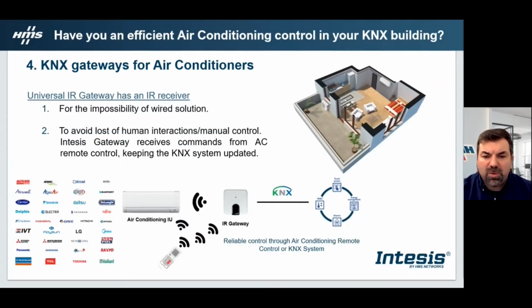Finally, we have our universal infrared gateway to answer to the impossibility of wired solutions. Beyond that, the infrared gateway is developed to minimize the loss of manual controls. As we can see in the image, when we change the temperature set point through the remote control, our gateway has inside an infrared receiver that will receive the command at the same time and will keep always the KNX system updated and with the accurate parameters of the AC. And our infrared gateways are compatible with most of air conditioning brands in the market.